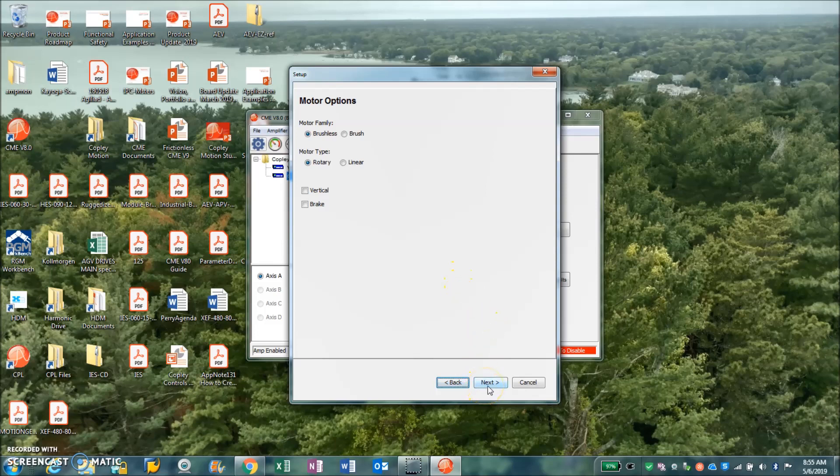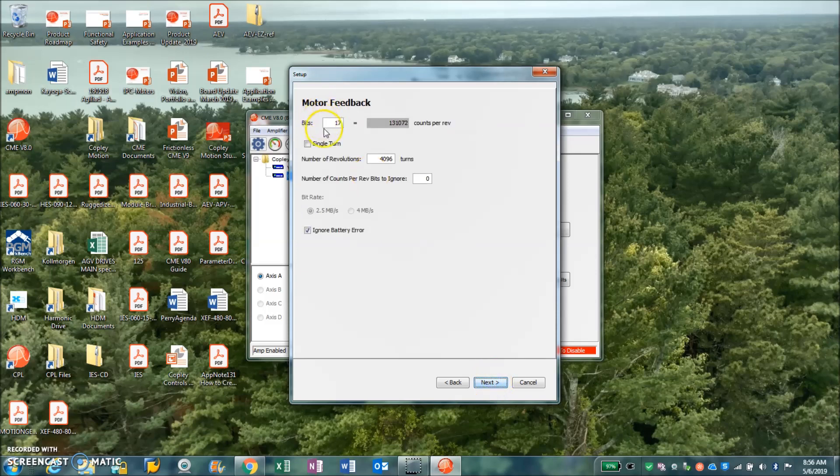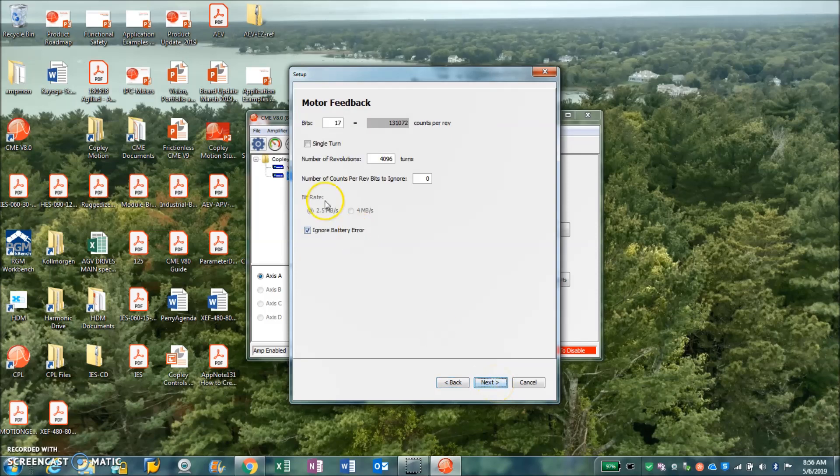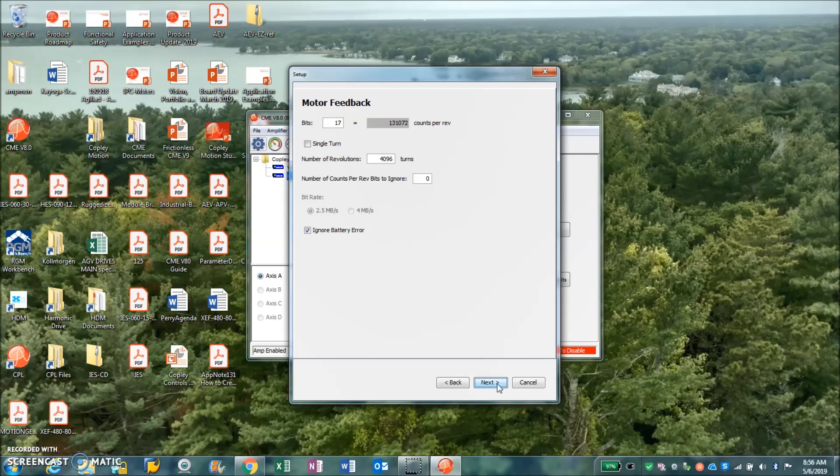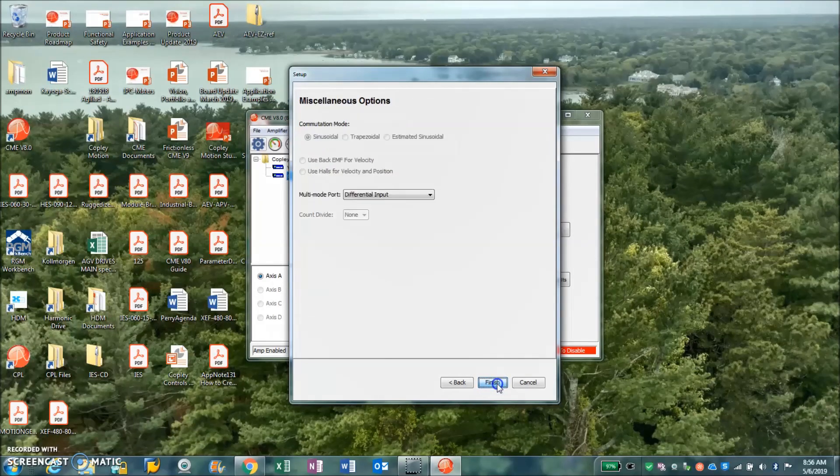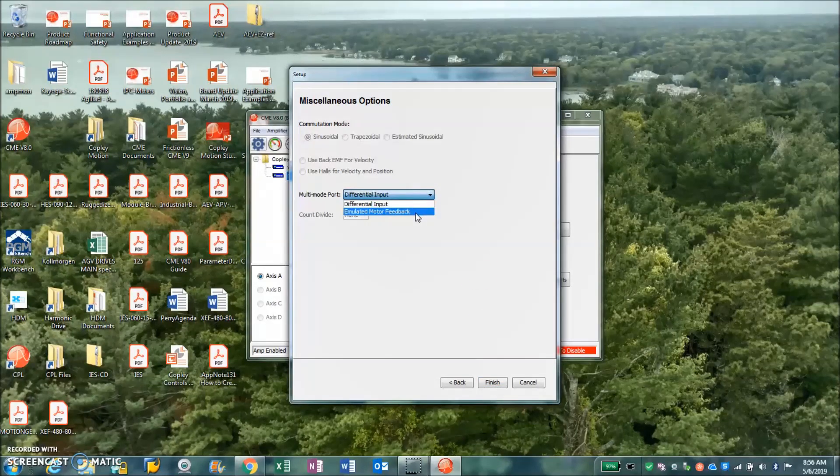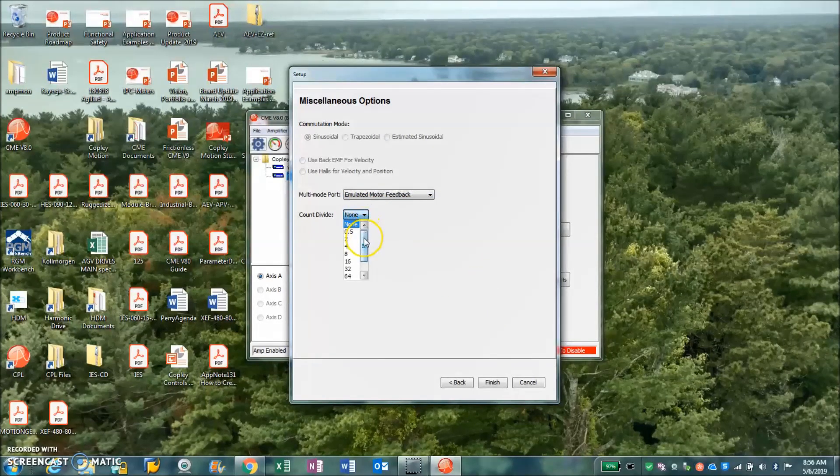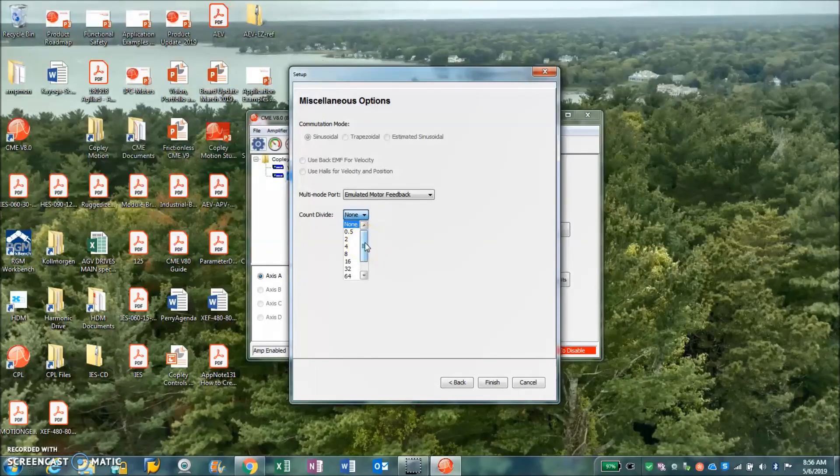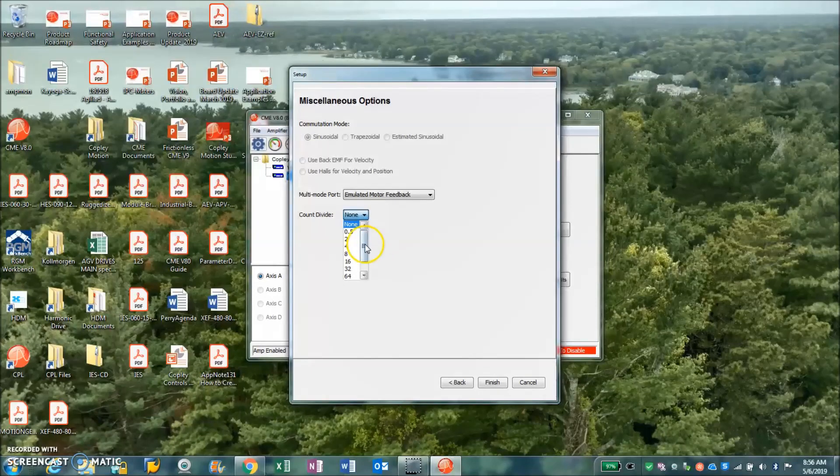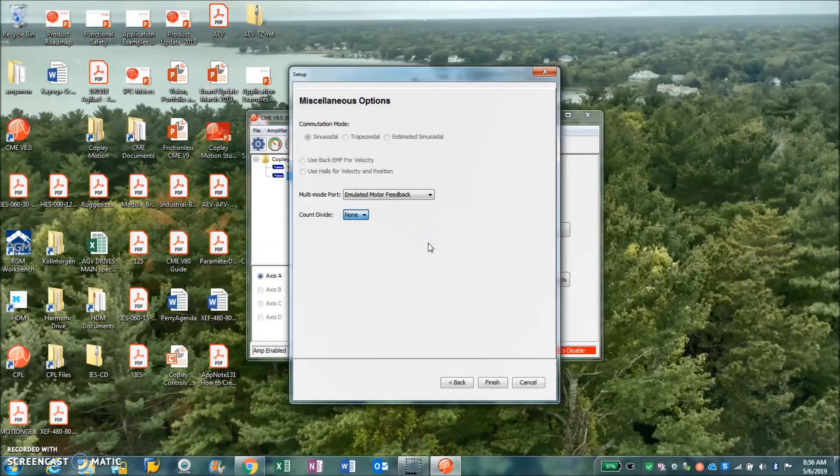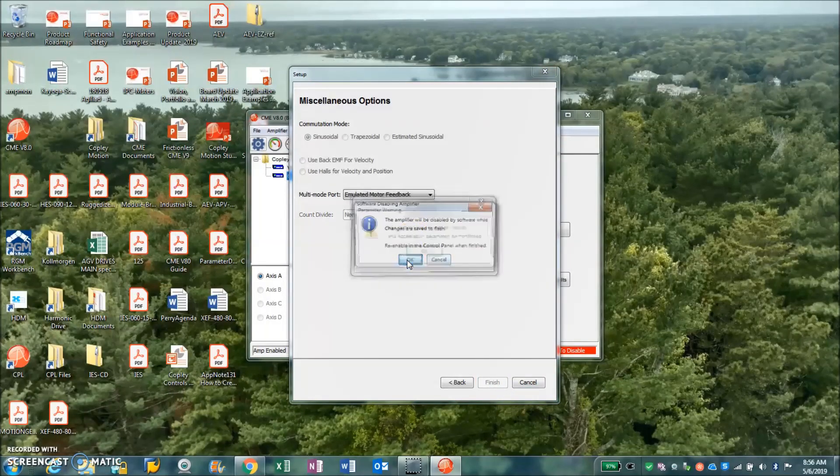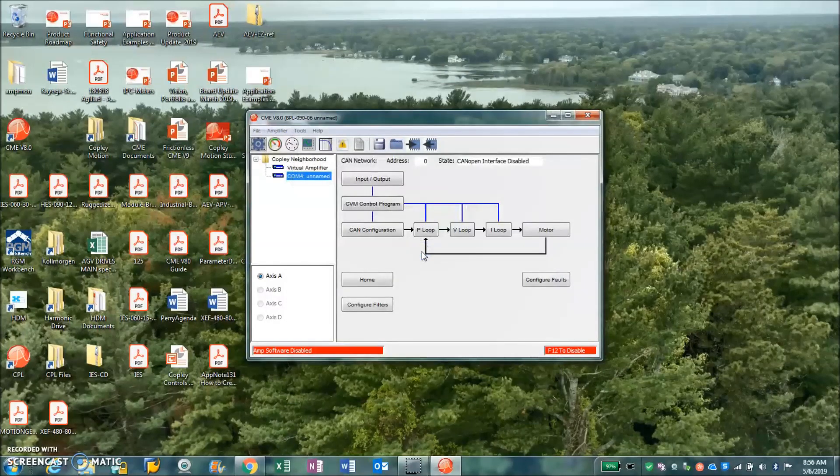The new and interesting thing is the motor information is right next to the feedback options, which is probably a more logical place to put this data. We can still access it from the motor screen. With an absolute encoder, I like to do an emulated output and you can divide the count - that's new, that's cool. So you got a 17-bit encoder and you can't handle 20 megahertz on your old controller, you can divide it down. 20 megahertz is probably a limit of where you want to be for your frequency out of a drive anyways.